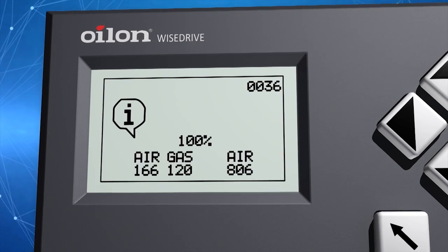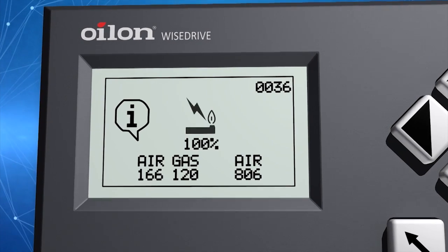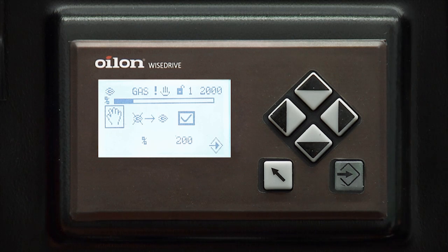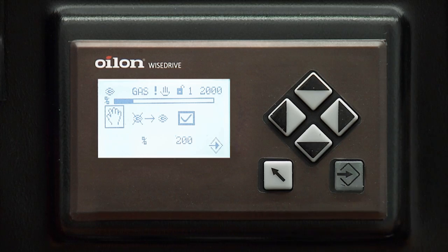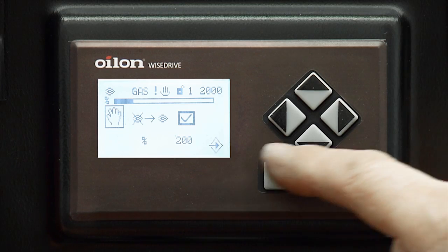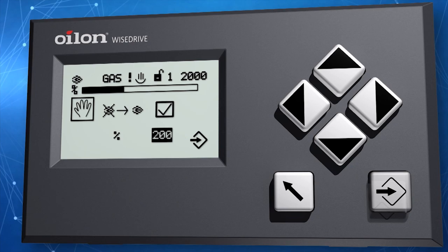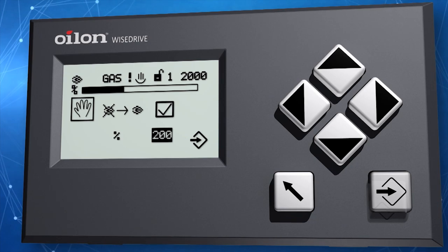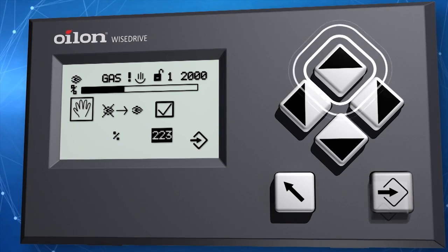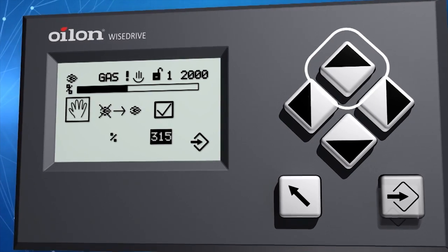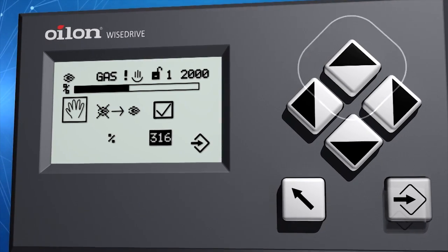The burner starts. After the burner has run to minimum capacity, you can increase the capacity manually. It is increased by selecting the capacity with the arrow keys. All actuators follow automatically. Note that at least one curve point must be set, otherwise the burner will not start.